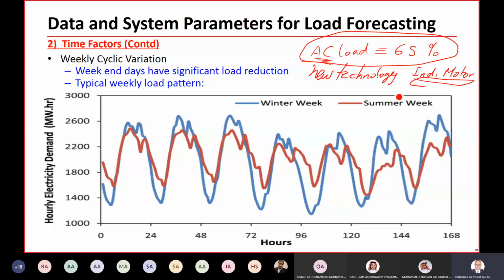We can use adjustable frequency drive instead of a constant speed motor, allowing you to vary the motor speed. You can also have new induction motor technology, replacing it with what we call the line start permanent magnet synchronous motor, which is more efficient than the induction motor. This reduces AC consumption, so new technology reduces the load.